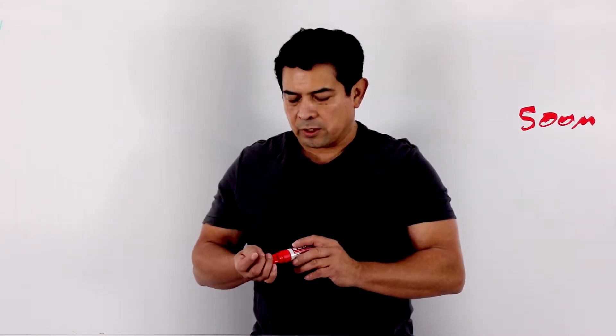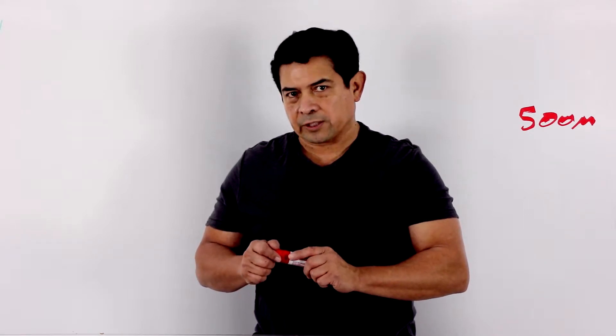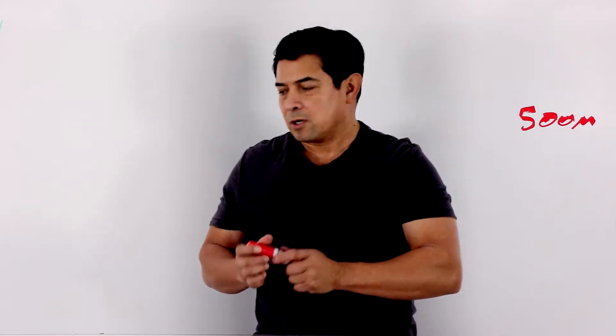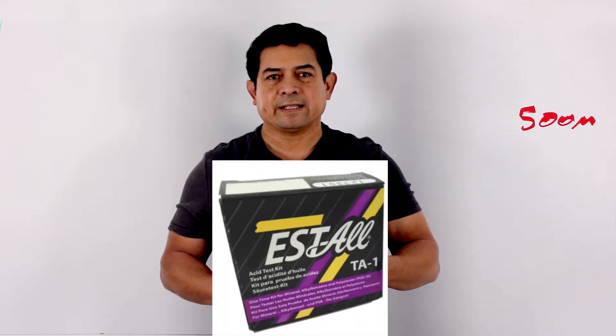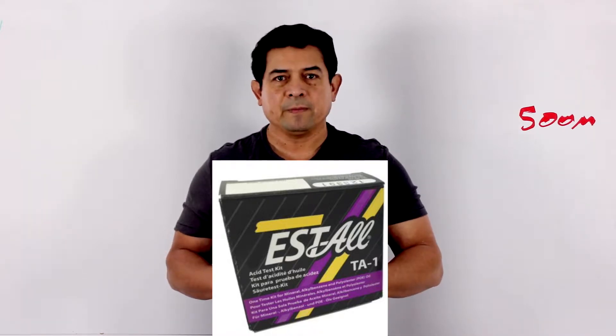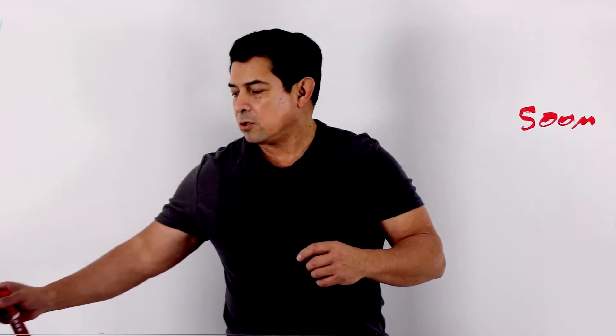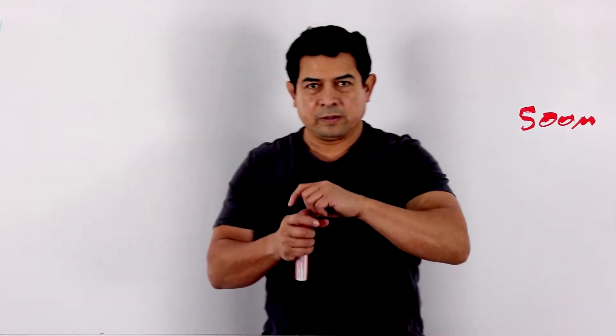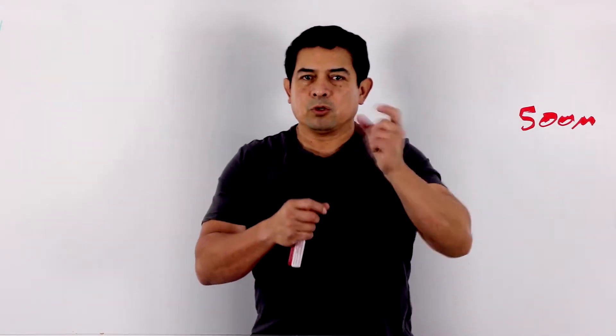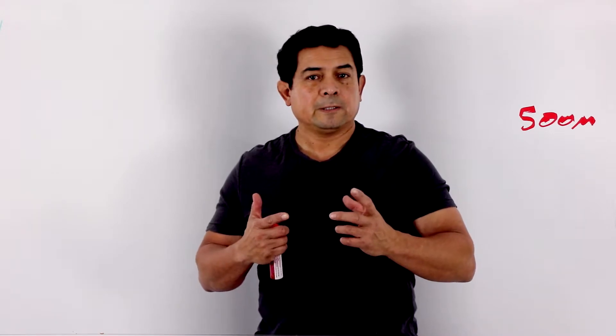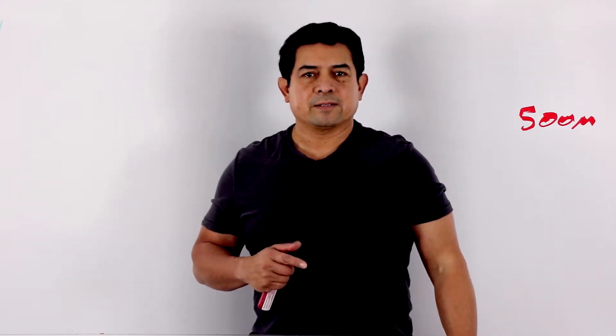But how do you know that you need to flush the lines out? That's another question. Well, one of the things you might want to do is you may want to test the system. You might want to do an acid test. They have different types. This is just one of them. But what you do is you take a little bit of oil, you mix it with, in this little bottle, and you shake it. If they change its color, then yes, you have acid in the system.